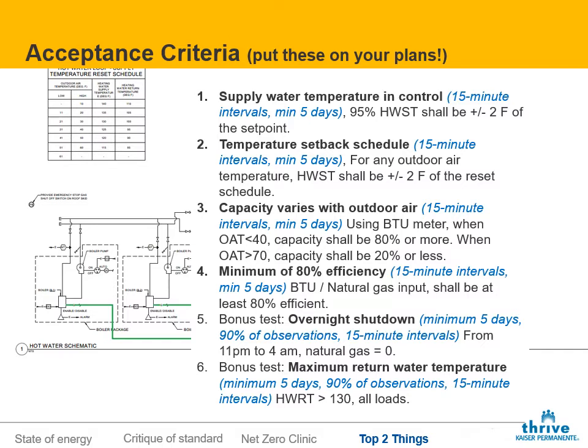You may not even be able to achieve your supply water temperature in control. Your chart will look like an earthquake, the delta T will be poor, and then you'll fail the efficiency test and you'll fail everything from that point, right? In fact, I like to say that testing a boiler in the wintertime is kind of cheating, right? Of course it's going to work when it's freezing cold outside. The real test of the boiler system and its responsiveness is like this afternoon when it's 55 degrees outside or 52 degrees outside, right?